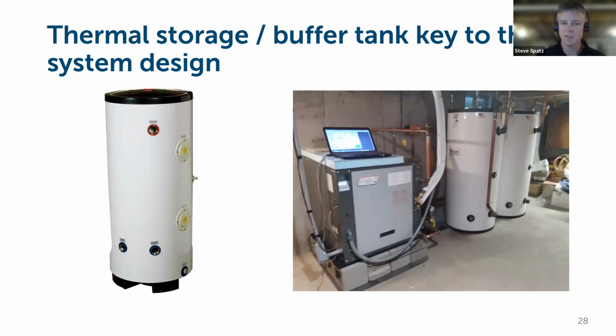That being said, there's a very small percentage of time of the year that these heat pumps will be seeing temperatures where they will, quote unquote, struggle or not put out as much BTUs, and their efficiency will drop. In those scenarios, if there is a high draw of BTUs from the buffer tank on the distribution side throughout the house, and the heat pump is not able to keep the set point in the buffer tank, there are electric resistance elements. That's what these two little guys are here on the tank. Those are electric resistance elements like you'd see in a traditional electric water heater. Those can come on and energize and heat the water to maintain the set point if the heat pump is not able to do so.